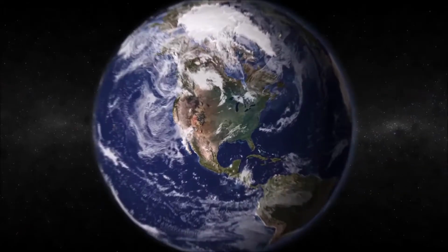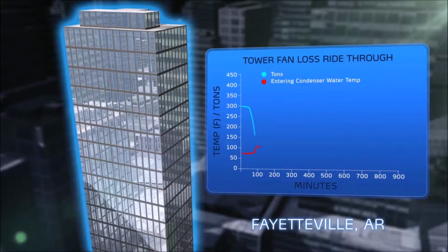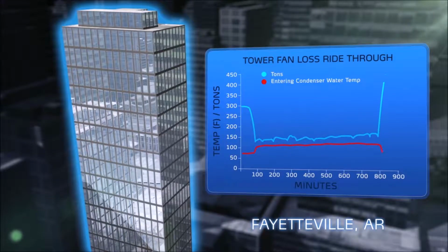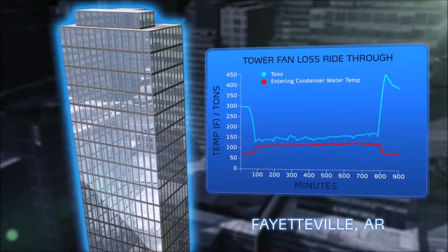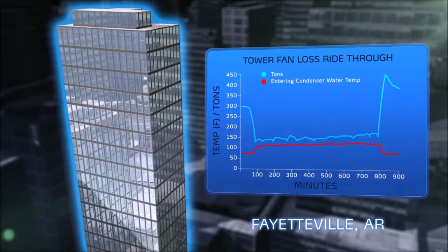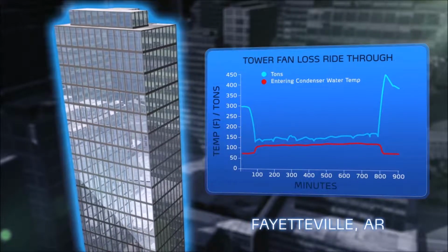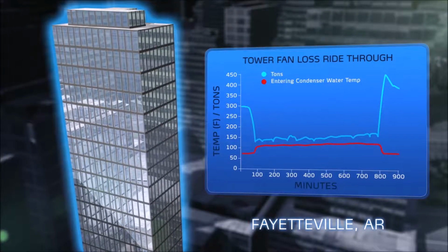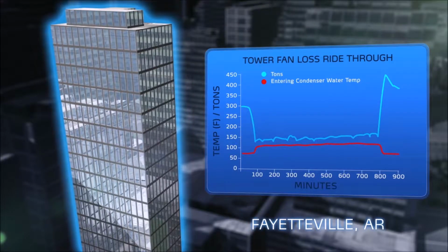In 2005, field data recorders in Arkansas documented a chiller operating without any operable cooling tower fans. The chiller endured entering condenser water temperatures of over 105 degrees during the 12 hours it took to repair the tower fan. The chiller operates through conditions where other chillers would simply shut down.